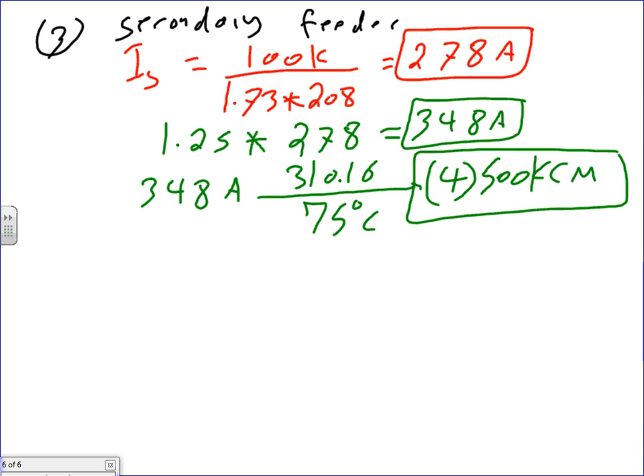And the code doesn't tell you either way for the transformer or the cable. It's a judgment issue. But because we size the transformer, I incorporate my 1.25 in the size of the transformer. I already oversize my transformer. And it makes more sense, guys, when you tie it to a panel. If you do it this way, you end up with a transformer that can give you 120 amps and a panel that's 150. So the transformer, no matter what you do, cannot give you more than 120 amps, but your panel is rated for 150, and the cable is rated for 150. So that 30 amps is worthless because the transformer will never be able to give you the extra 30 amps.